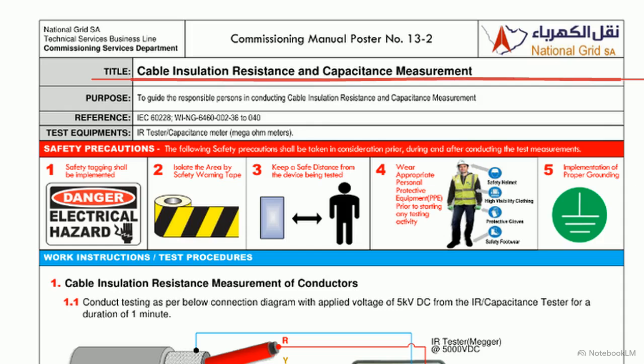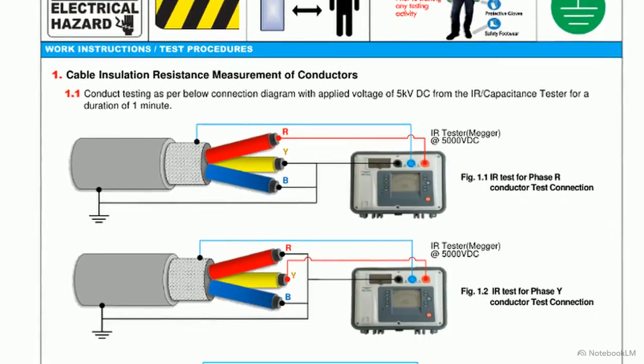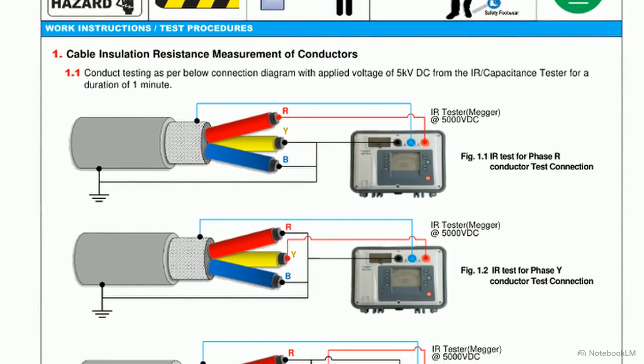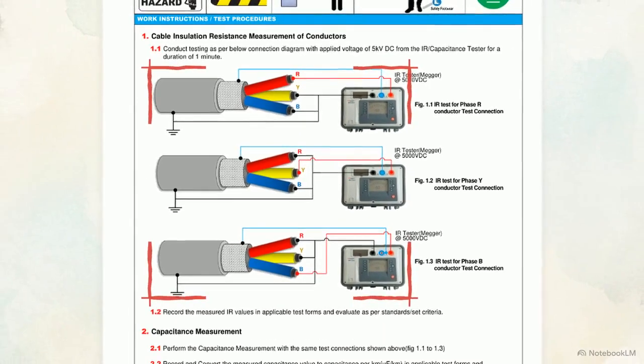This schematic details test 13-2, measuring cable insulation resistance and capacitance. After isolating the cable from bus bars, surge arresters, and connected equipment, the megger applies 5 kV DC for 1 minute to each individual phase connection to record baseline insulation resistance and ambient conditions.